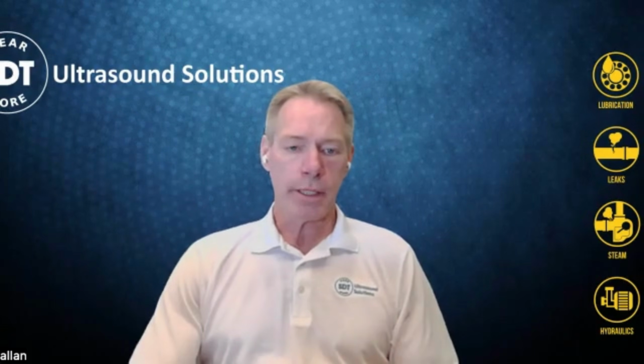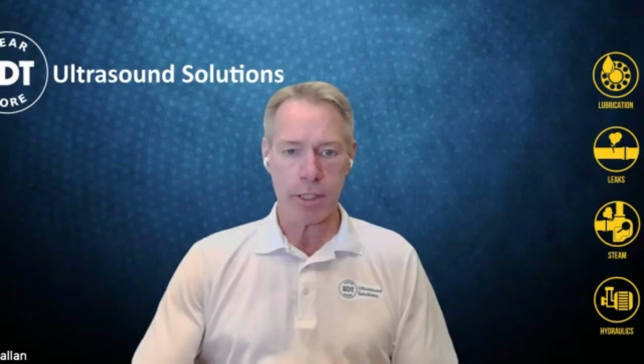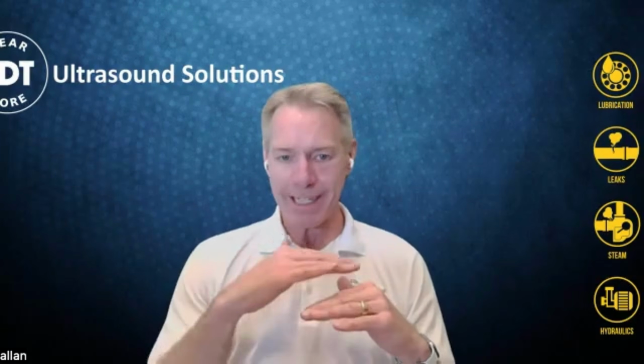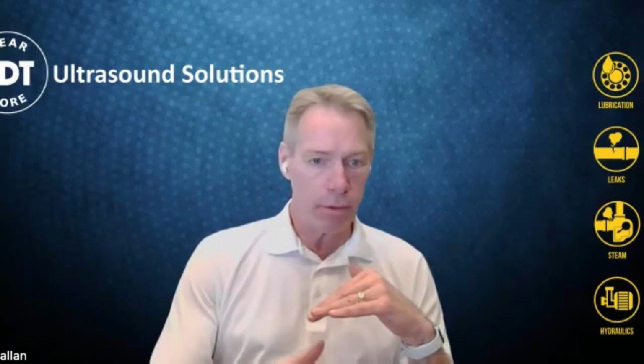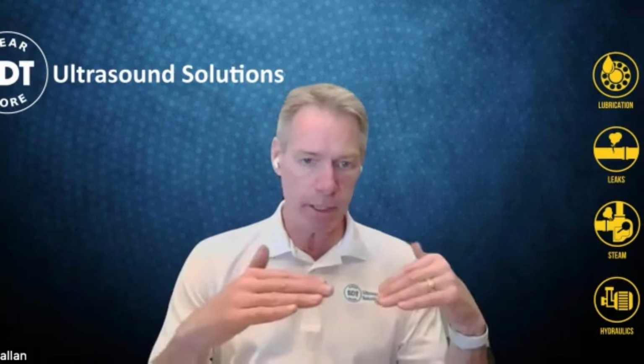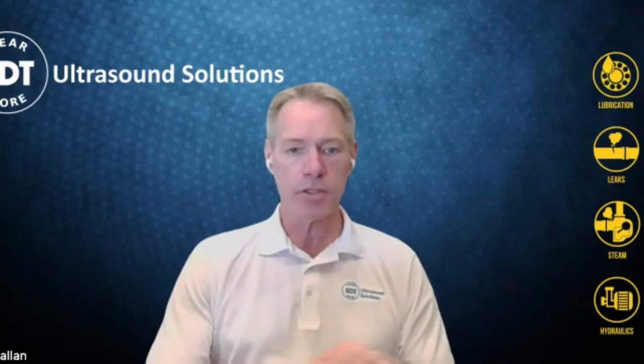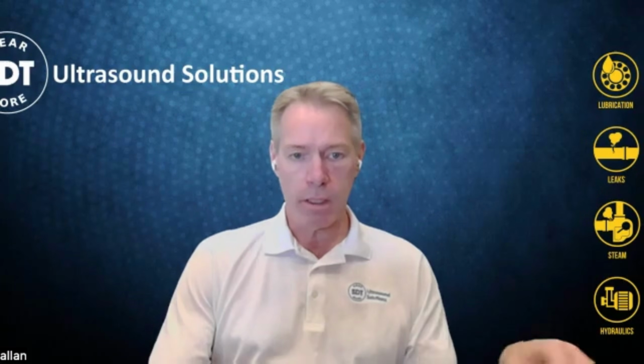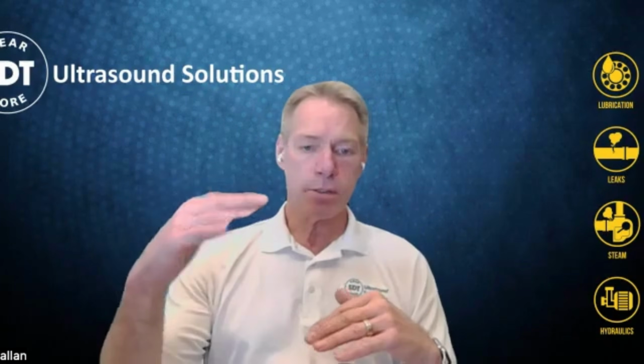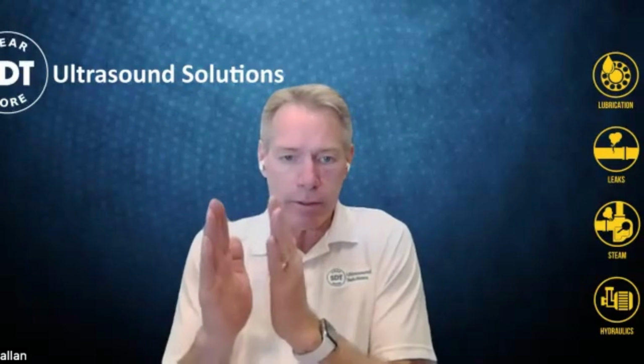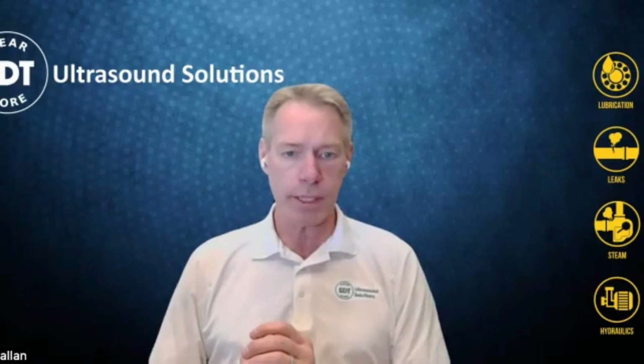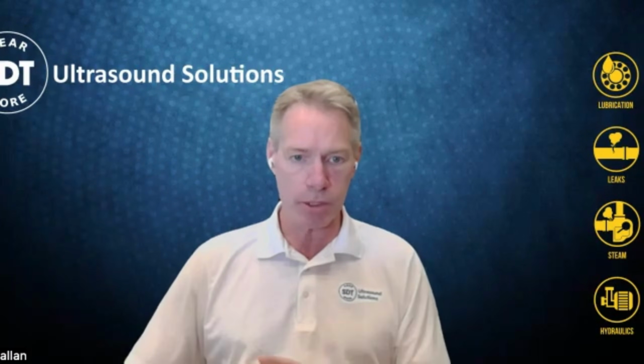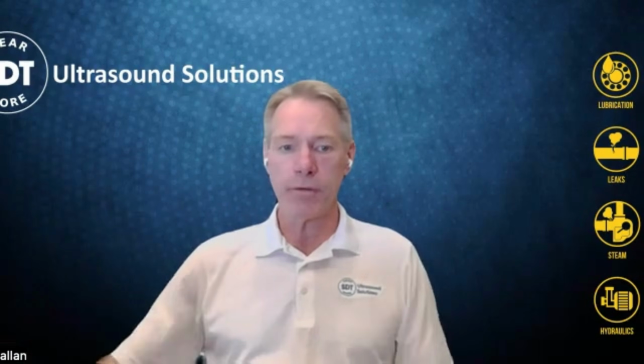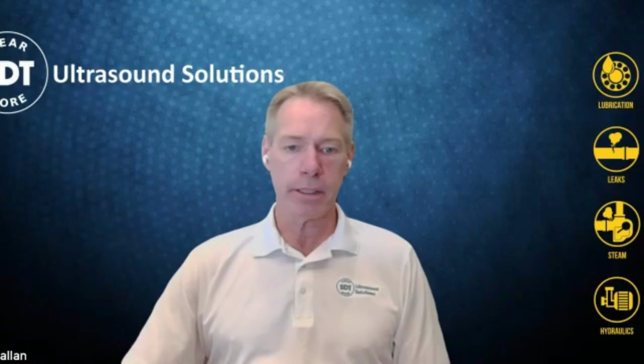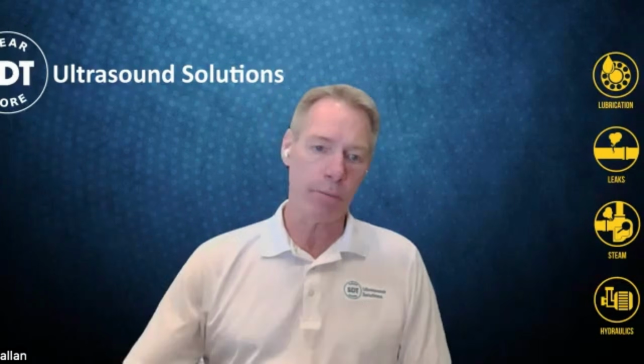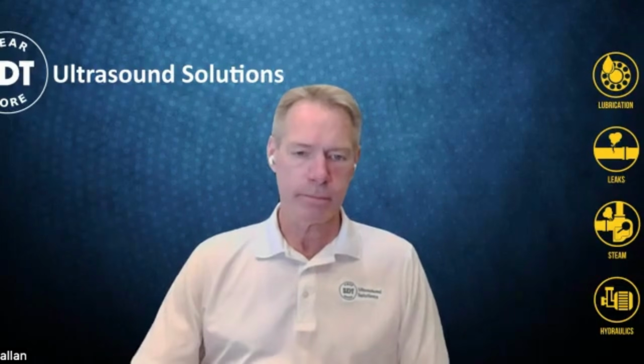Well, what an ultrasonic detector or an ultrasonic data collector does is it uses a high filter to cut off everything below 38 kilohertz. So if it's below 38 kilohertz, the instrument's completely deaf to it. And if it's above 42 kilohertz, it's completely deaf to it. So we've narrowed down to this really small band of ultrasound where all of this friction, impacting, and turbulence is occurring. We've eliminated everything else so we can just hear exactly what it is we want to hear without being interfered with by other things. I hope that's clear.